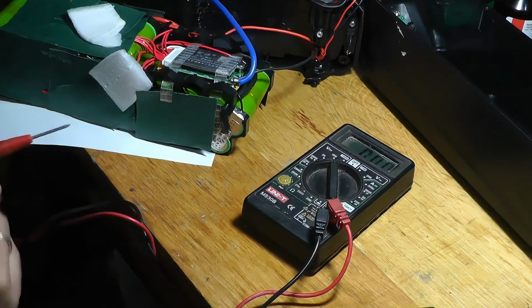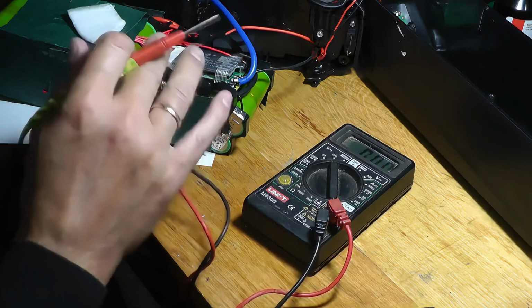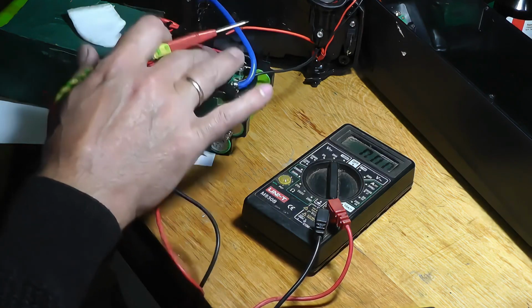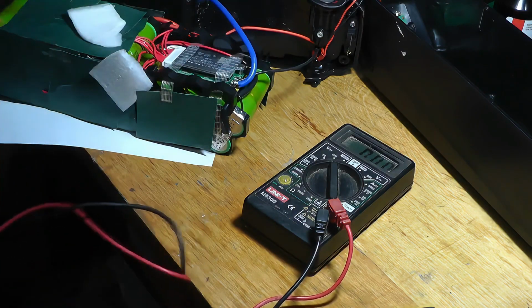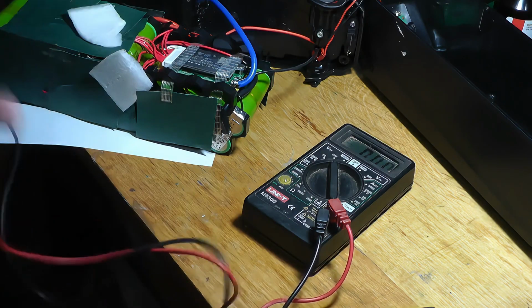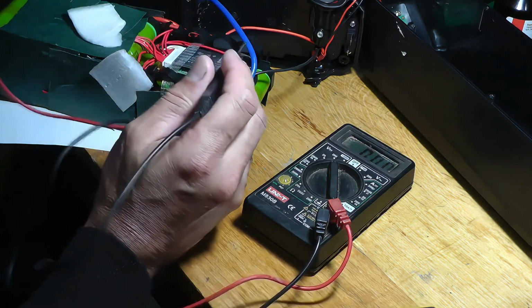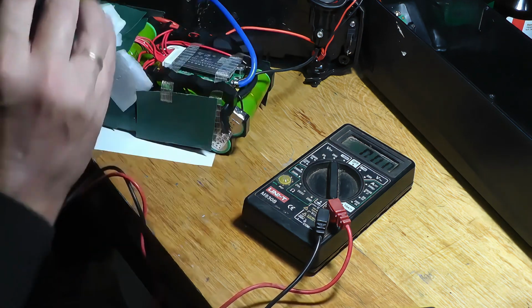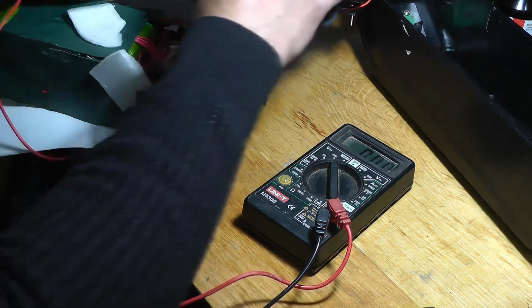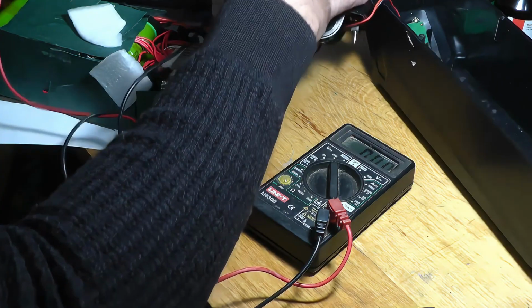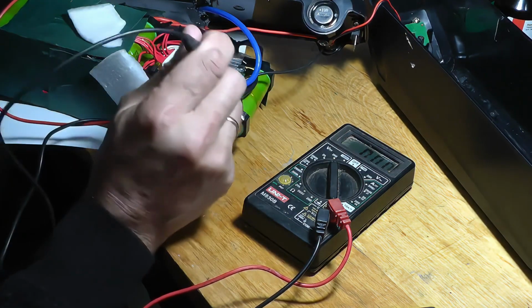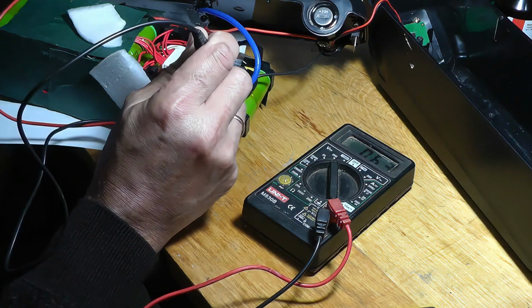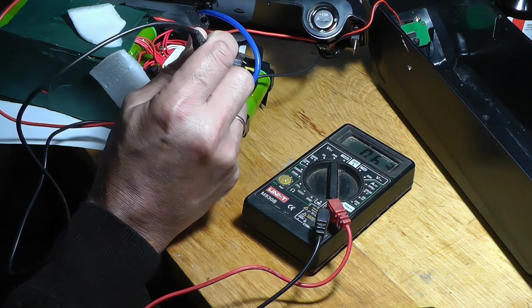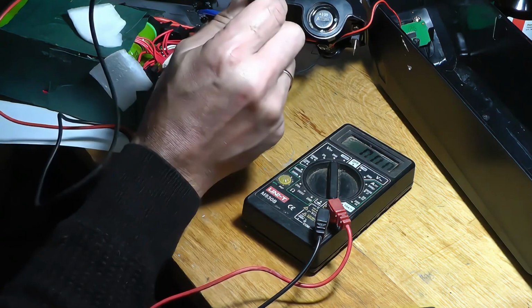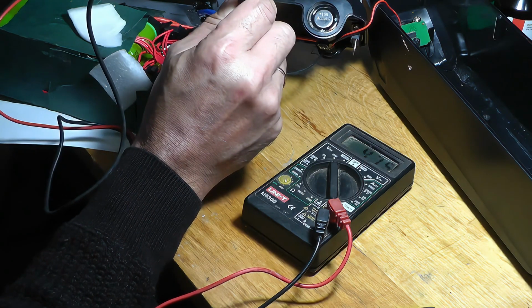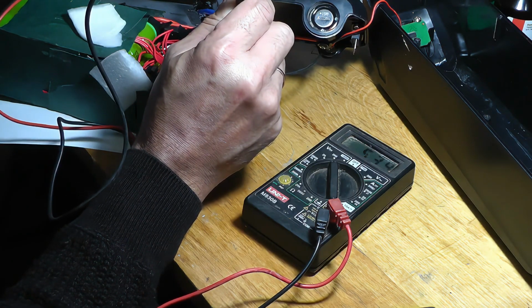After this, you need to check the current voltage on the entire battery block and what voltage is entering the BMS controller board. Connect the negative to the board's input and the red positive to the battery's power output externally, then check the voltage. The voltage at the BMS board's output is low, and at the input it's 52 volts.